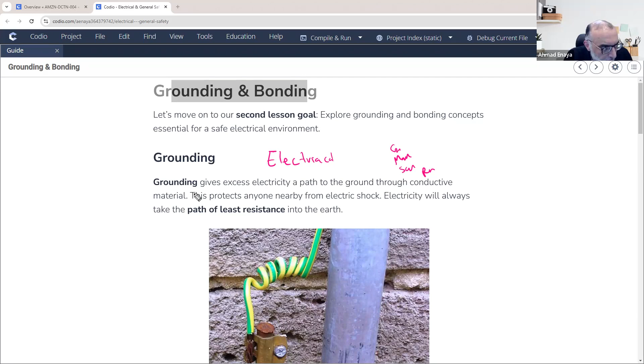There is another related concept, which is bonding. Bonding is mainly, we want to make sure all devices in the rack are all connected together, so there is no voltage difference between them. There is no electricity difference between devices in the room. Bonding is connecting them together. We want to make sure that the chassis of your switches, your routers, your servers, and also the rack itself, the door of the cabinet, the raised floor, any components in the room are all bonded together. So with this bonding, we make sure the electricity level is the same in all devices in the room.